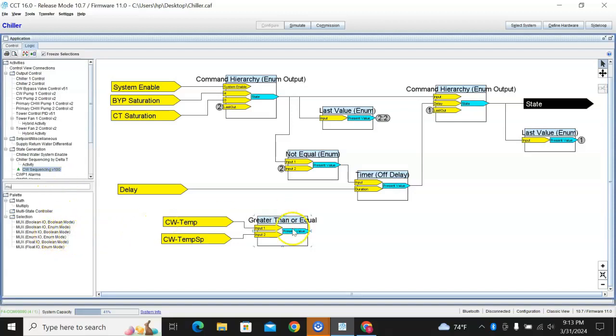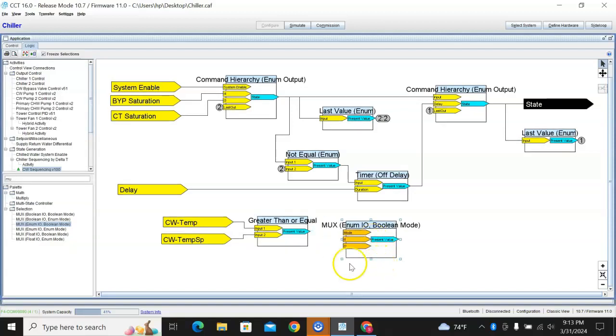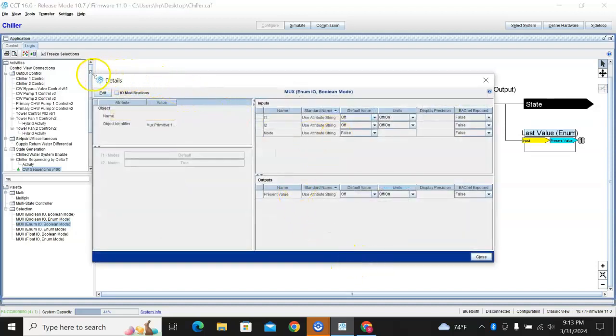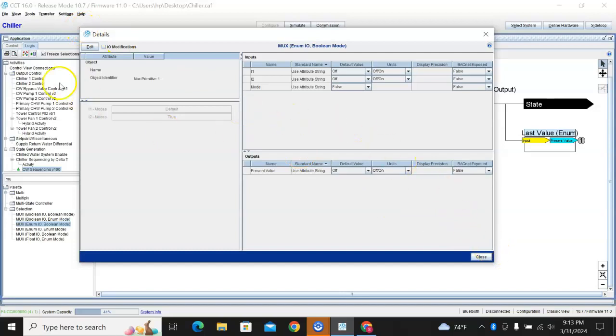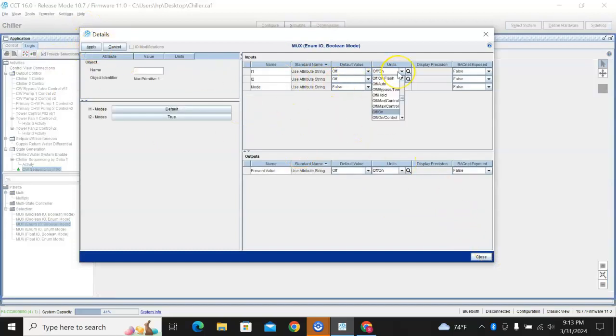So I have a Boolean mode. This greater than or equal to is going to give me a true or false out. That's a Boolean. And then I need an enum state. So an enum IO Boolean mode is the one I need. I'm going to drag that over there, connect this with that. I have to go inside the mux block here, and then I'm going to change these to off, bypass, tower. I'm going to put this one in tower. I'm going to put this one in bypass.